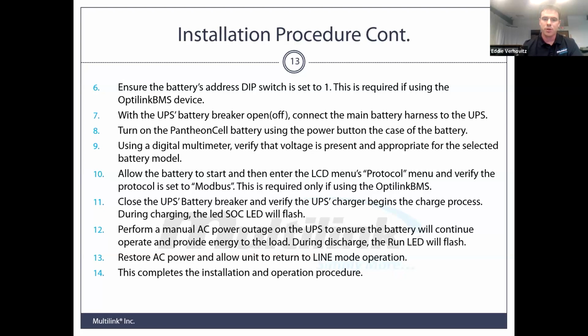From here, we want to turn on the Pantheon cell battery using its power button on the case of the battery. In our demonstration, our on-off button will be shown as a silver on-off button. Once the battery turns on, we want to verify the voltage between the terminals and verify that it is present and appropriate for the selected battery model. If you have selected a 36-volt model, we want to see the battery voltage at 36 volts or greater. If it's a 48-volt model, we want to make sure that the voltage is also 48 volts or greater.